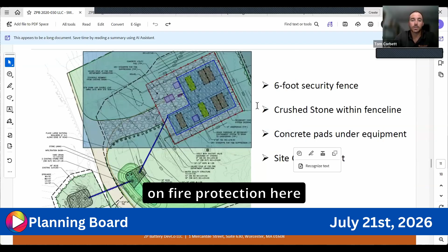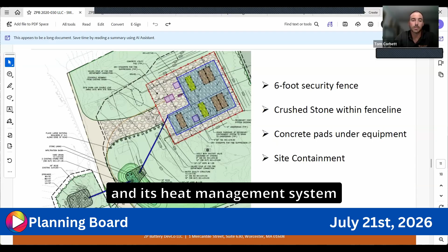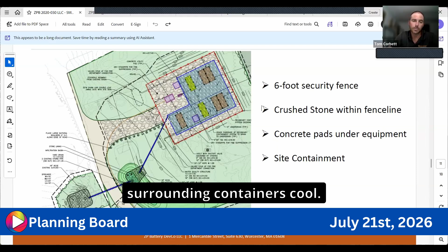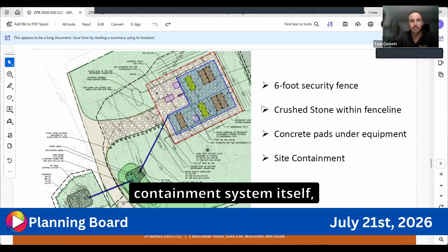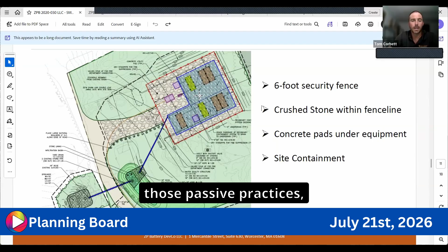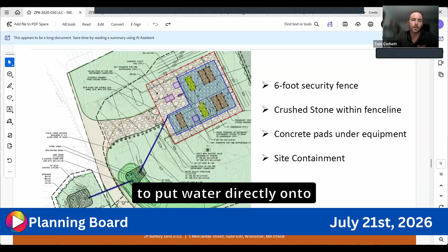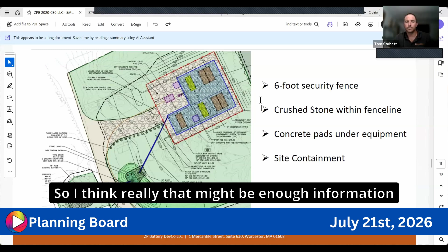If one were to go into thermal runaway, effectively you let the system do as it's supposed to with its battery management system and heat management system, allowing the energy to burn out, while focusing on protecting surrounding exposures and keeping other containers cool. That's the purpose of the secondary containment system - to capture the water used during those passive practices, typically a fogging pattern, not copious amounts of water poured on the containers. It's actually highly advised against to put water directly onto an affected battery container, for multiple reasons, one being that you could make the problem worse.